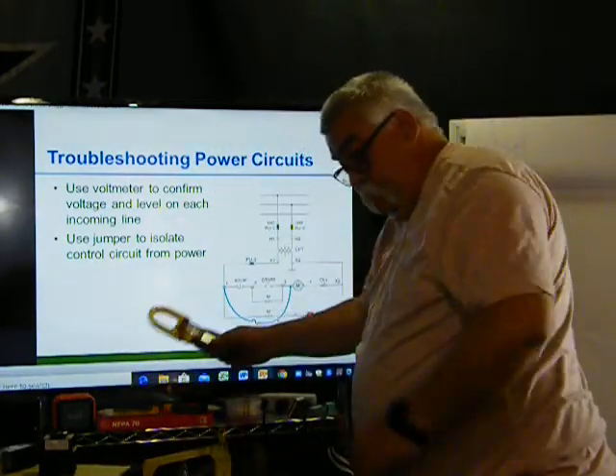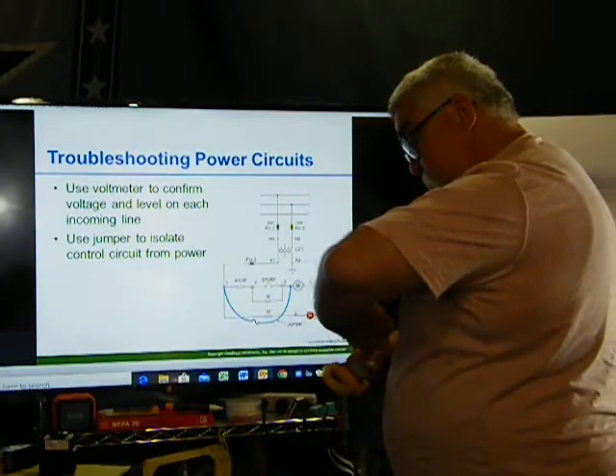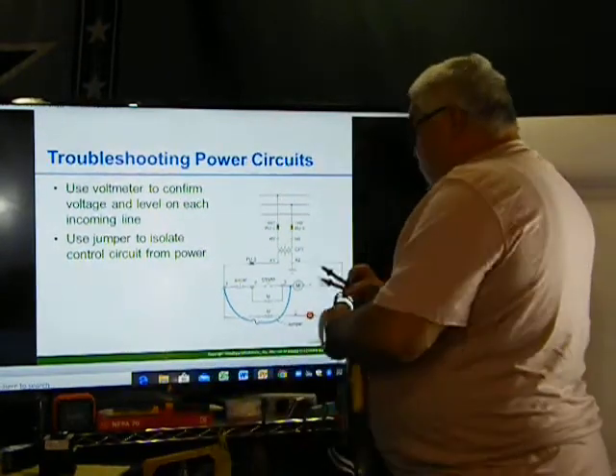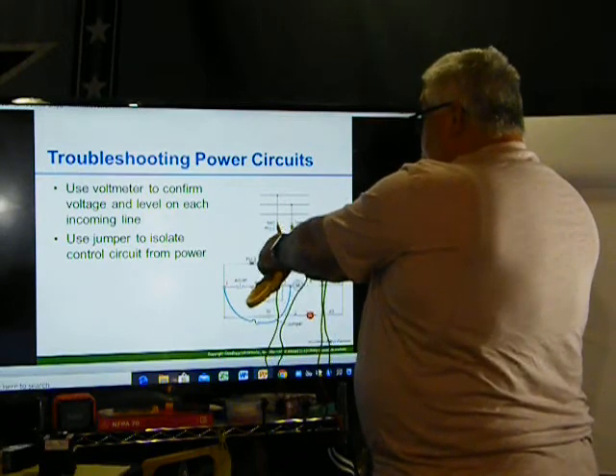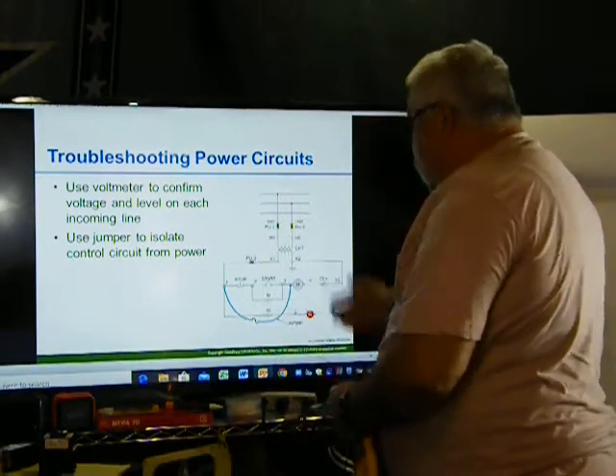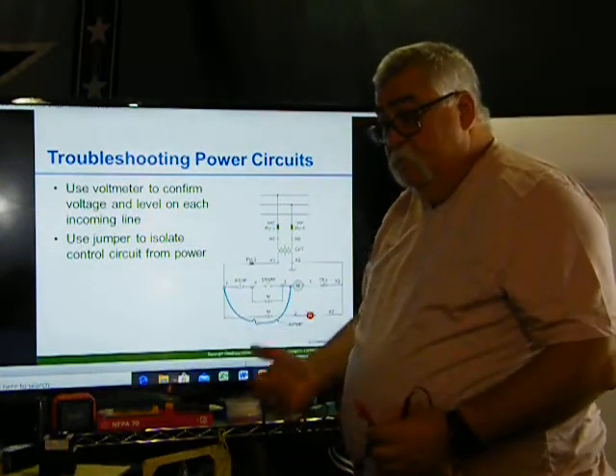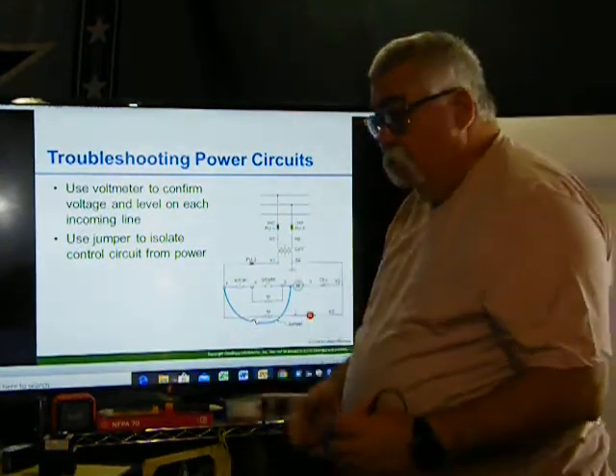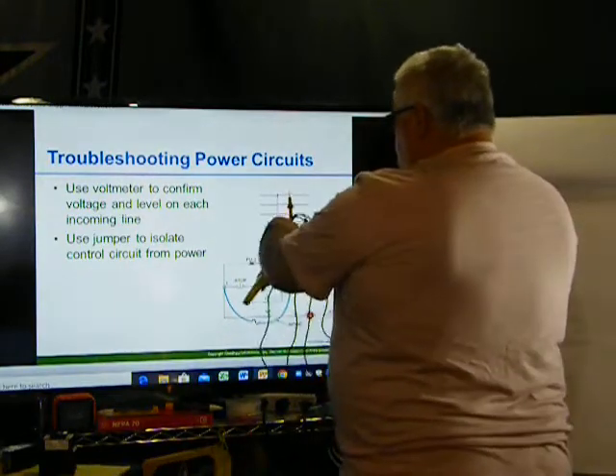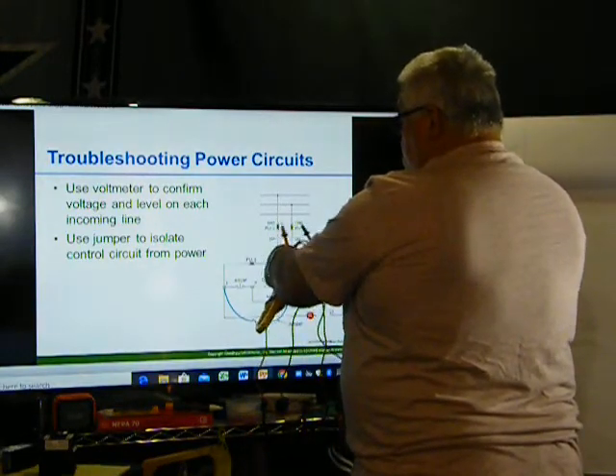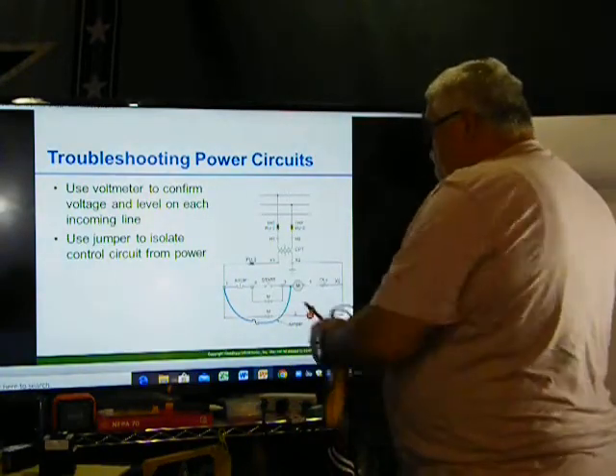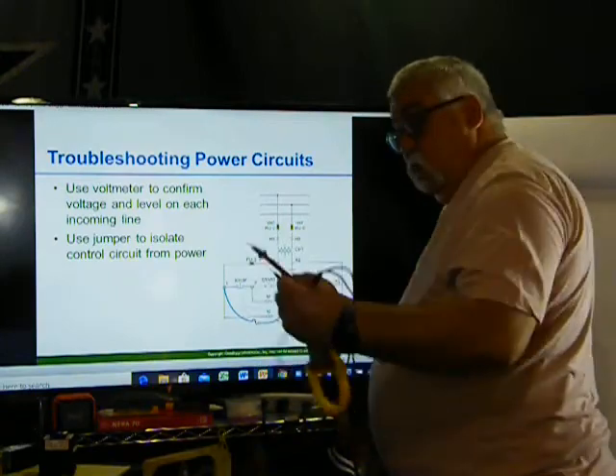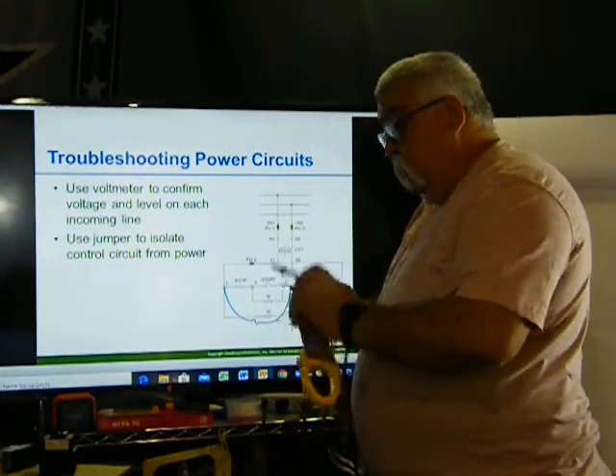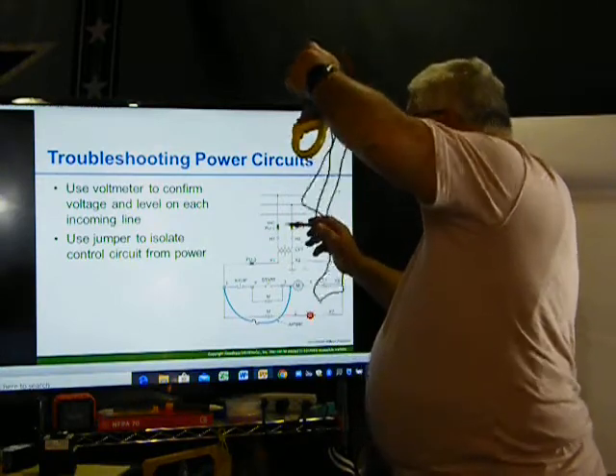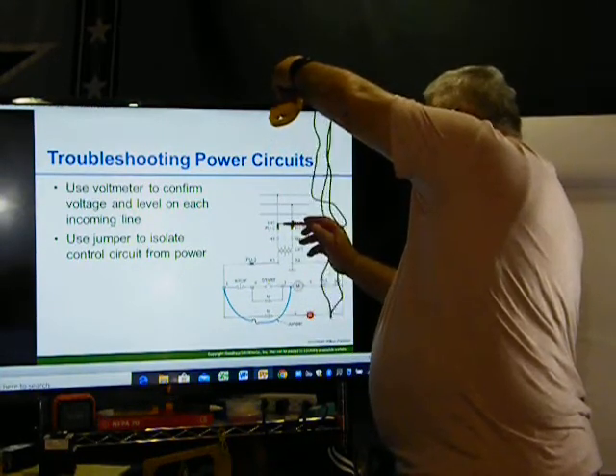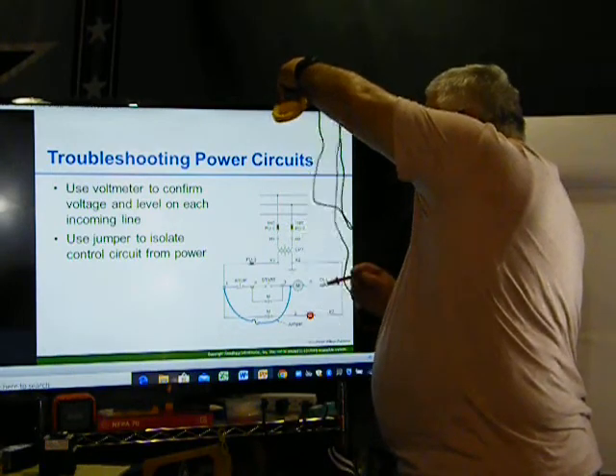So with my amp probe, I want to verify that I have power coming in at the top. So let's say this is a 240/480. I'm just going to say voltage out there. If I come up here and go across my fuses, I should have 480 volts. If I go to a grounded part, so I've got conduits coming into it, I touch a conduit with one lead, and now I touch here, I should have 240. I touch here, I should have 240.